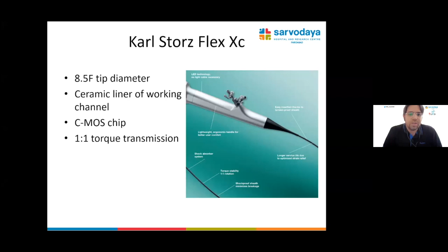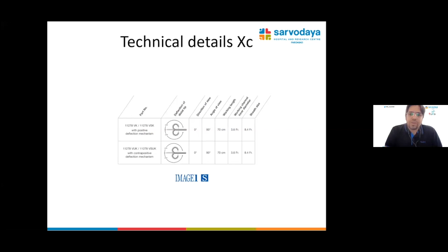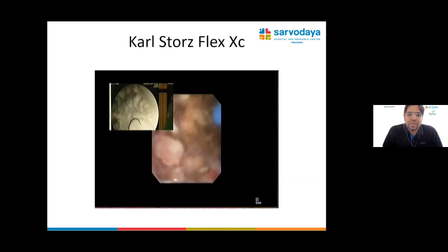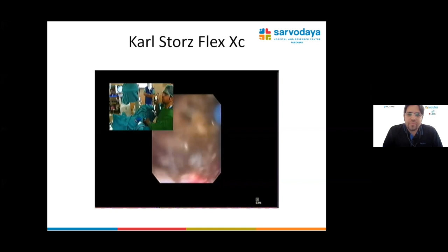Talking about technical details, the angle of view is slightly more than V3. It is 90-degree. Working length is 75 centimeters. Working channel inner diameter is 3.6 French, and the sheath size is 8.4 French. So this is the image quality we get with the Karl Storz Flex XC. We can see excellent maneuverability. As you can see here, I'm actually fragmenting in the lower pole with the scope bent, and you can see excellent vision quality there.